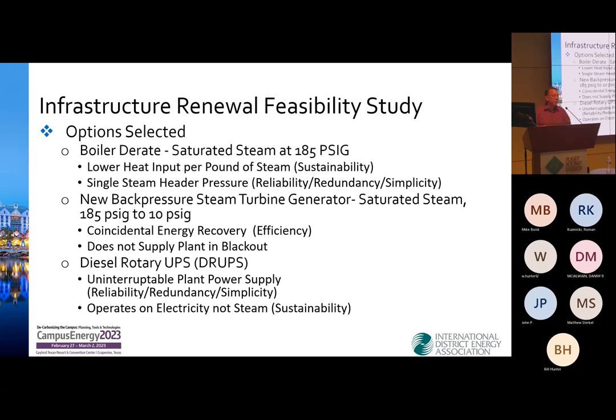But it was spending more and more of the year down for maintenance and repair. It was installed in '68. One month a year in the middle of summer for scheduled maintenance is fine, but 4 or 5 months out of the year down was unacceptable, and the hospital was getting nervous. So we opted to replace it, which also makes the plant more efficient, because if you have to make steam to heat the campus, you can send it through a turbine generator to make electricity - a great example of co-production using a single energy source.